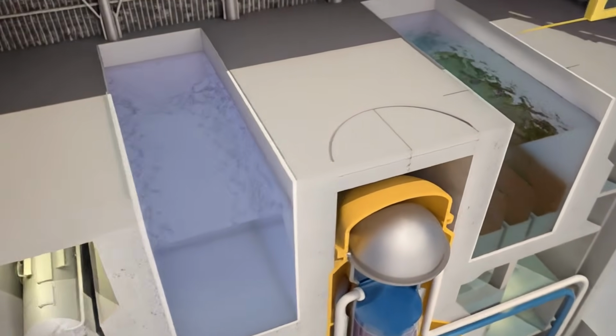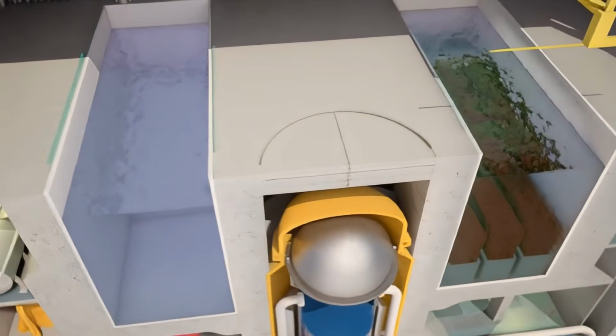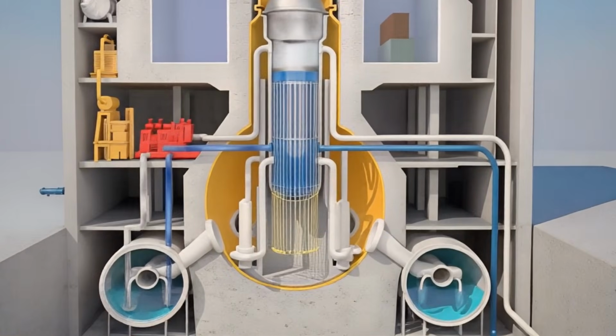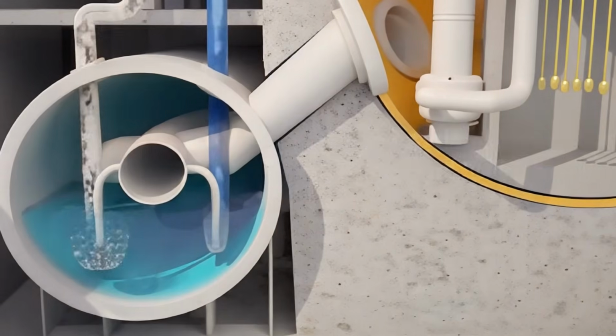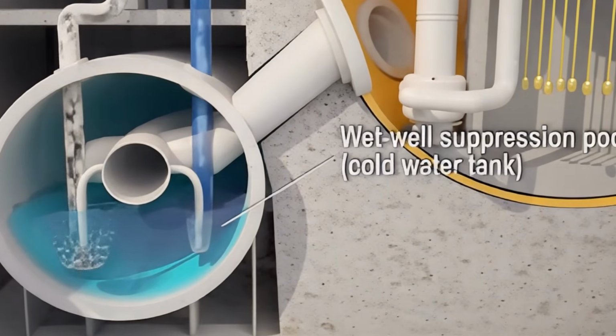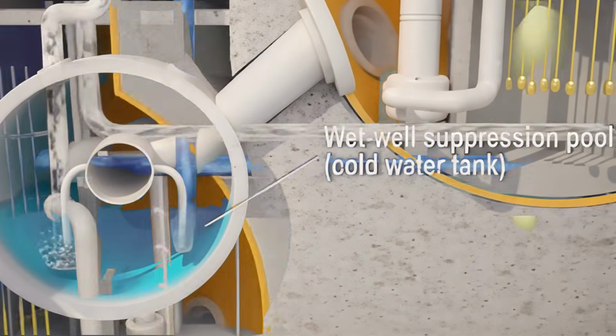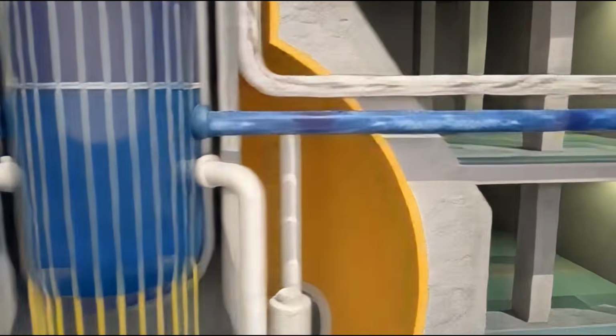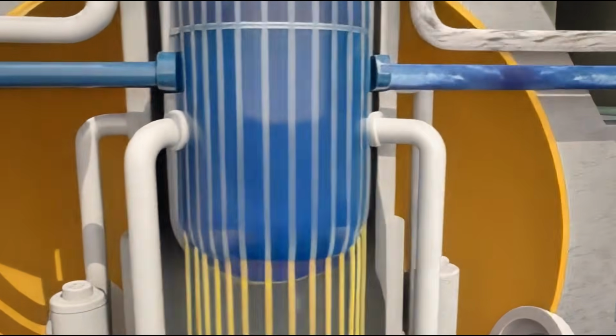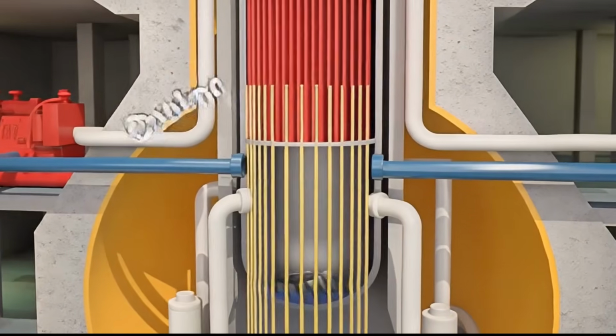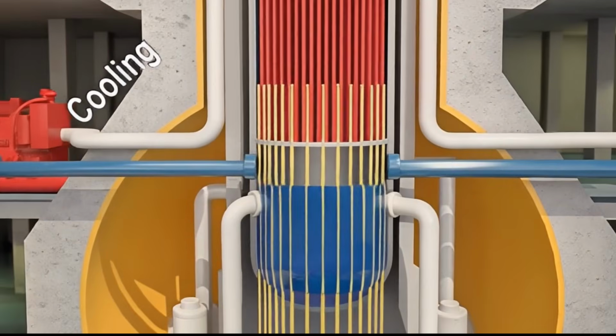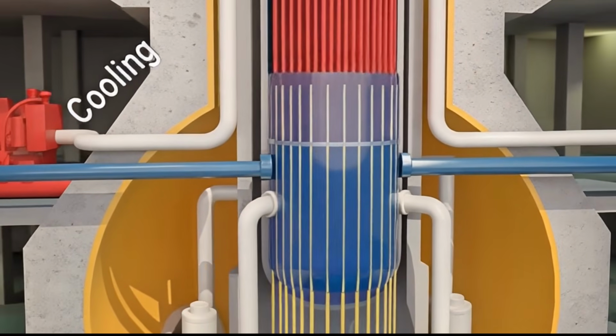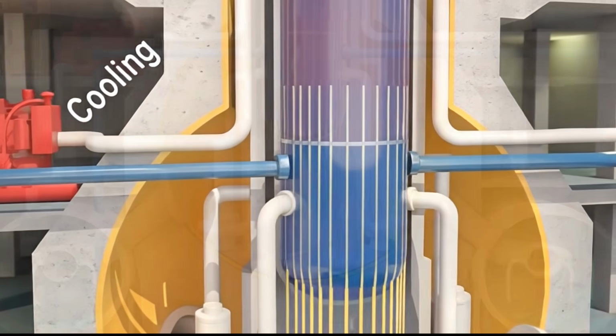The containment of these reactors possessed a relatively compact design, featuring a toroidal structure partially filled with water, whose function was to condense steam in case of an accident, reducing pressure inside the primary containment. The problem was that the total volume of that containment was relatively small compared to subsequent designs. This implied that a rapid increase in temperature and pressure could completely saturate it within a few hours.